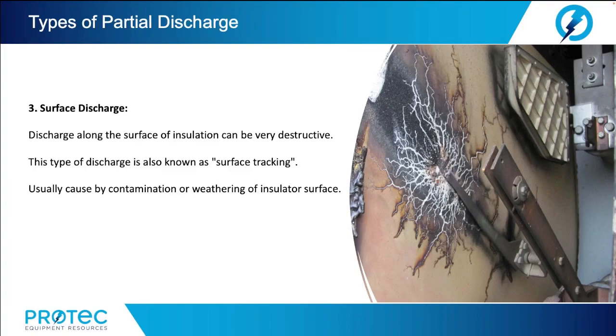This can happen on any medium and high voltage equipment. Surface discharges most commonly happen when the dielectric strength of the insulation breaks down in high humidity environments or when poor maintenance and cleaning of equipment lead to this phenomena. Moisture intrusion is also a common cause of surface PD.